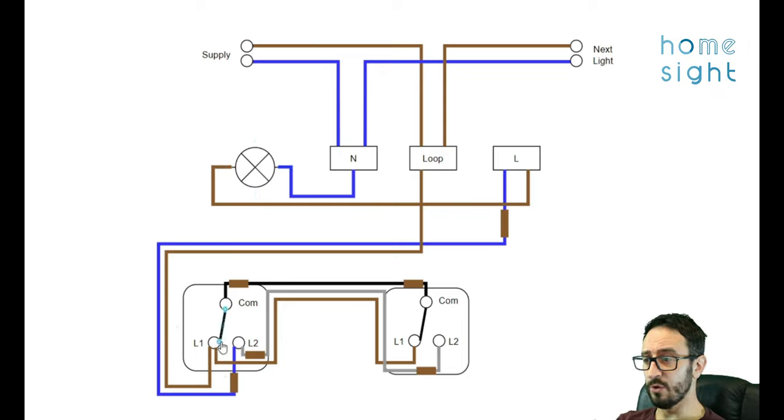So with them both in the L1 switched state means there is no electricity getting to our bulb. So if we were to move this one over to our L2 now the electricity coming down the brown wire is not connected to our common but it is going to go down this other brown wire to our other switch onto our L1 terminal up to our common across our black wire down from the common to L2 ultimately onto this blue wire which is going to complete the circuit through our switch live terminal here and onto the brown.